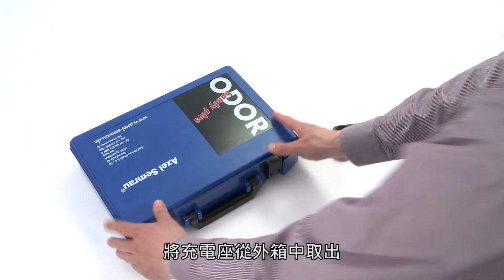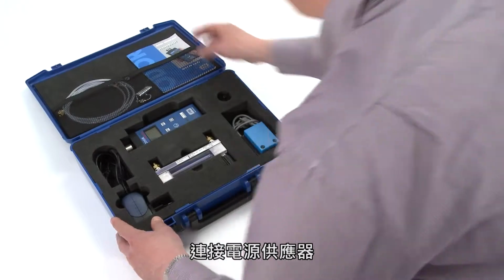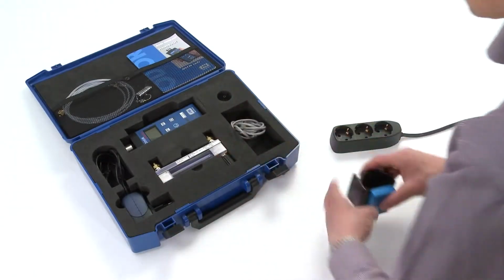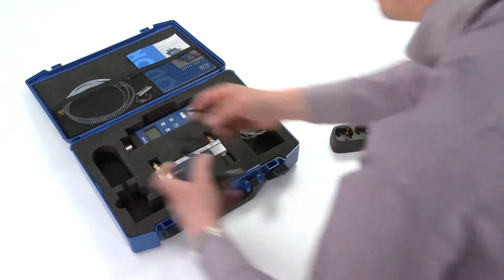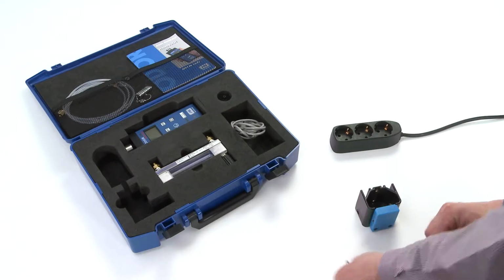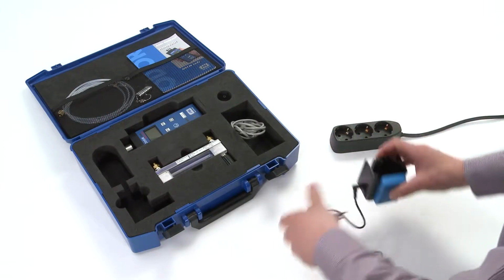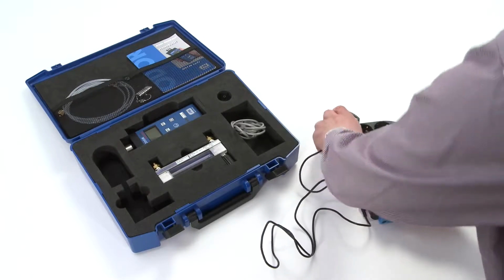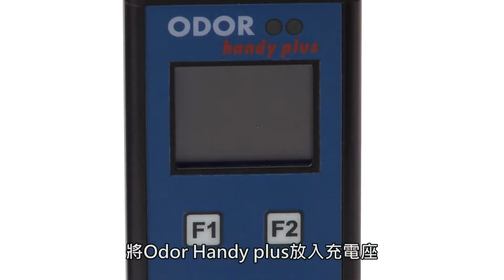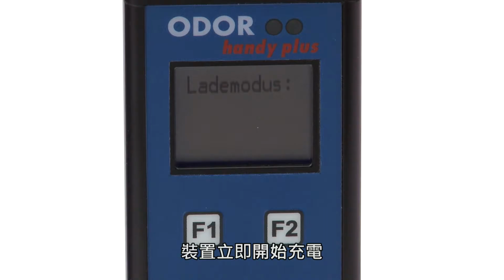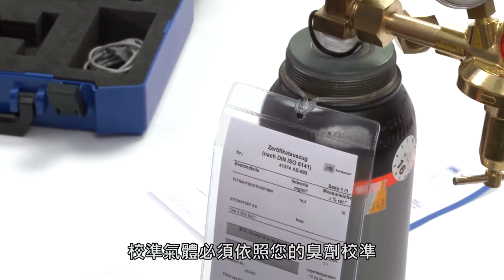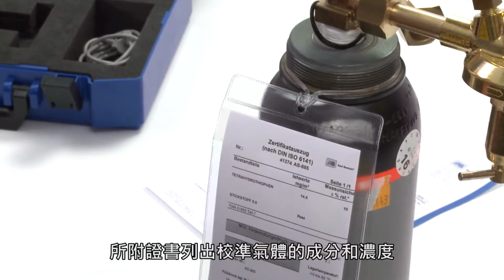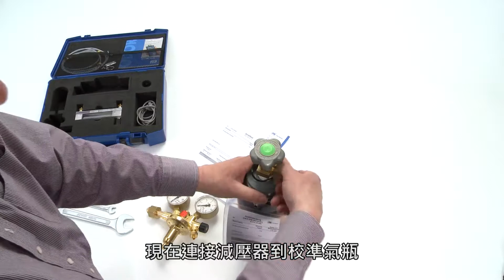Take the charging station out of its case and connect it by means of the power supply unit. Put the Odor Handy Plus into the charging station and the device immediately starts charging. The calibration gas has to be calibrated to your odorant. The attached certificate lists the composition and concentration of our calibration gases. Now connect the pressure reducer to the calibration gas bottle.